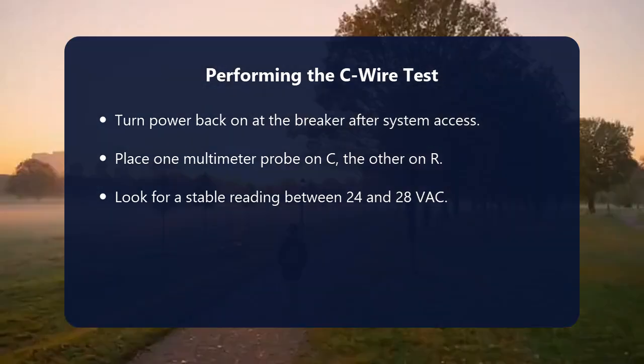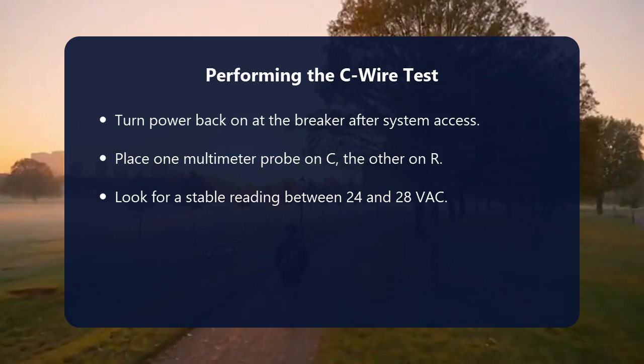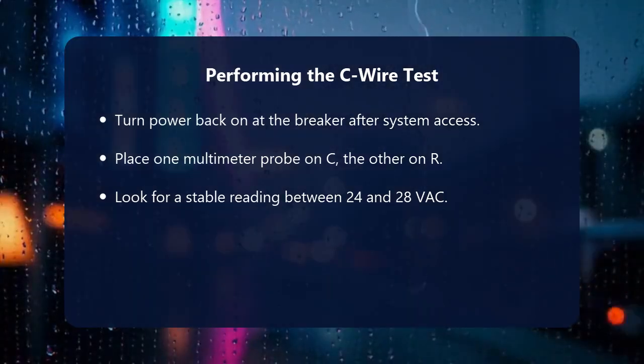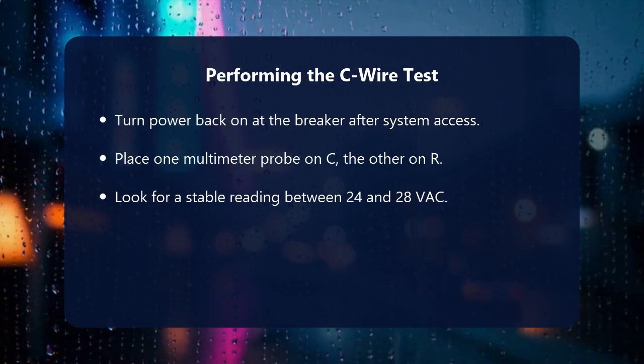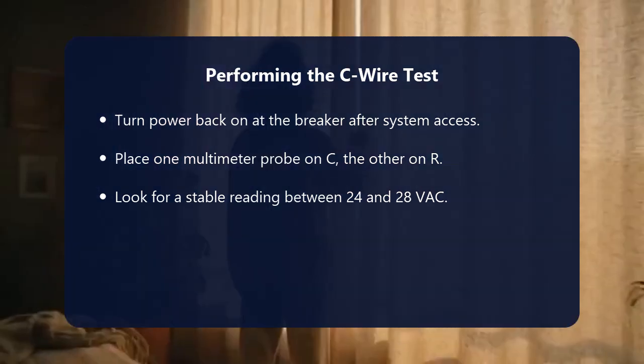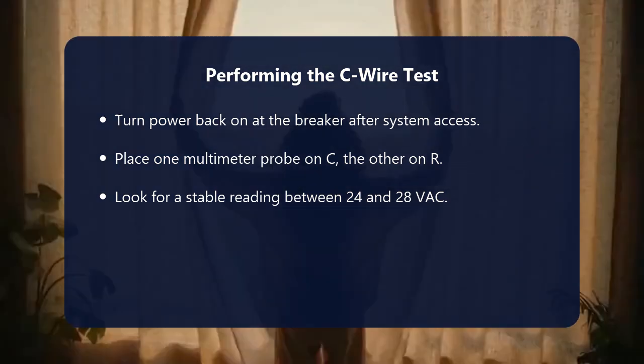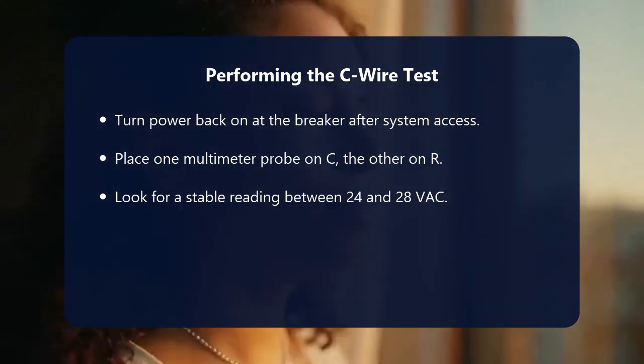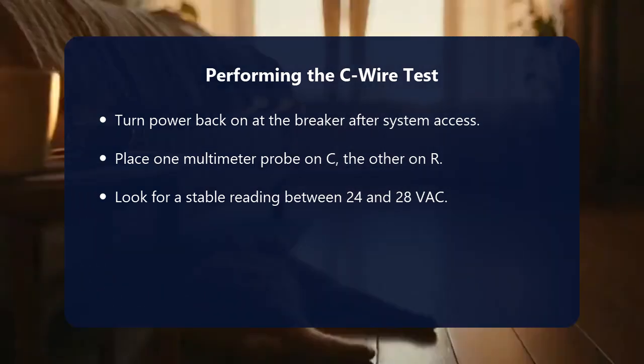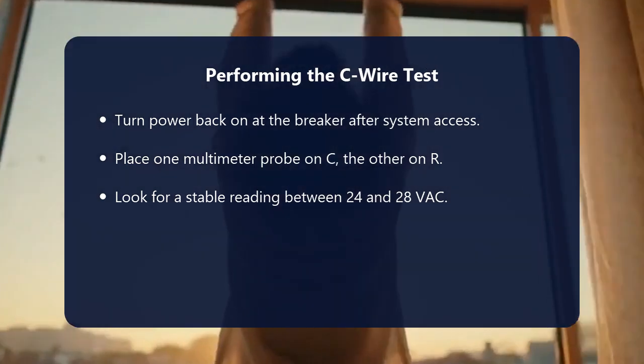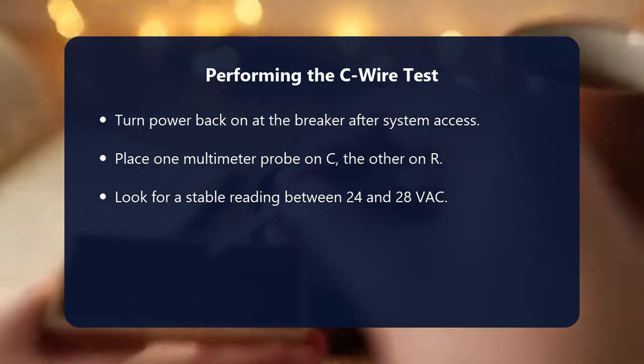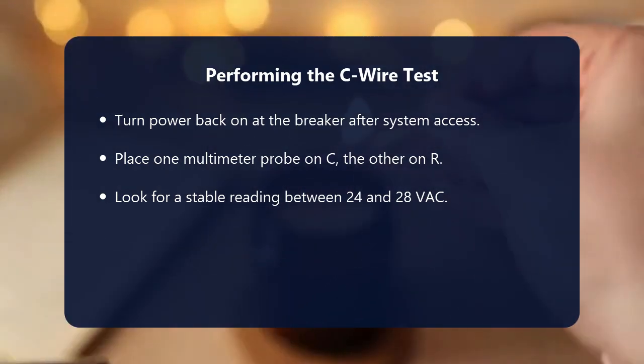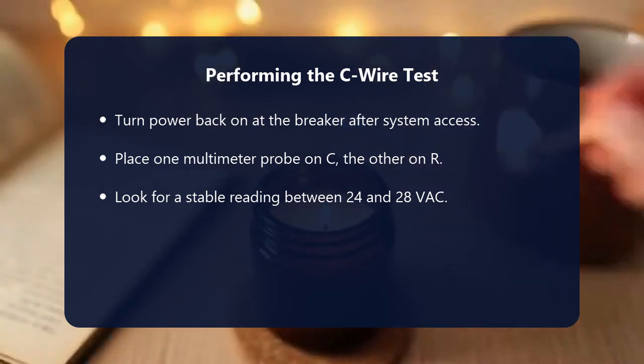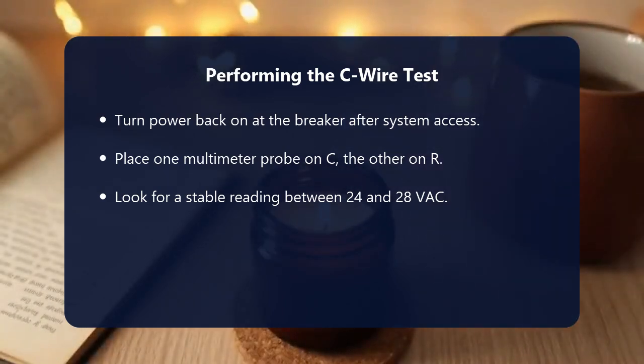With your multimeter set to AC voltage, turn the power back on at the circuit breaker. Now, carefully touch one probe of your multimeter to the C terminal and the other probe to the R or RH/RC terminal. Be careful not to short any terminals with your probes. Observe the reading on your multimeter's display. A healthy C-wire circuit should show a voltage reading between 24 and 28 VAC. This reading confirms that your C-wire is indeed receiving power from the transformer and completing the circuit back to the R terminal.